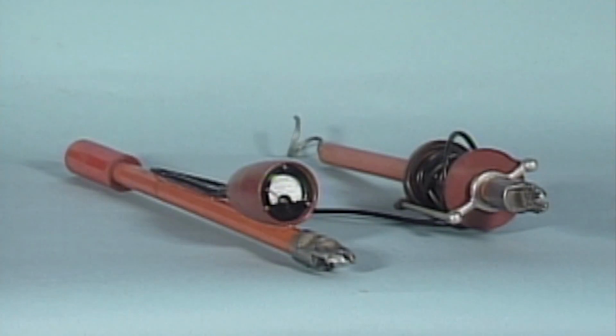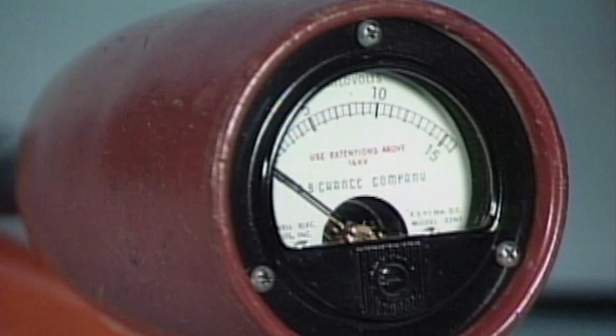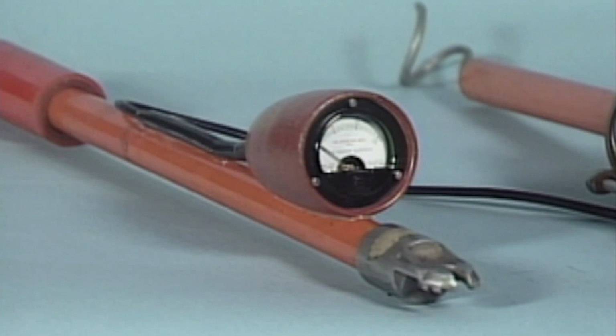A phasing tool is a device that is designed to give a specific voltage reading. It generally consists of two probes attached through a meter by a reel of insulated wire. In order to protect the meter and yourself, make sure you use a phasing tool with a range that can handle the highest possible voltage you expect to find.